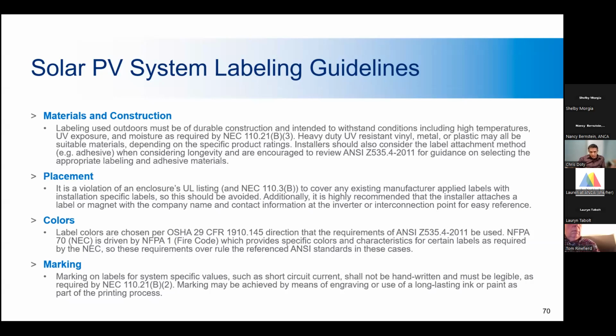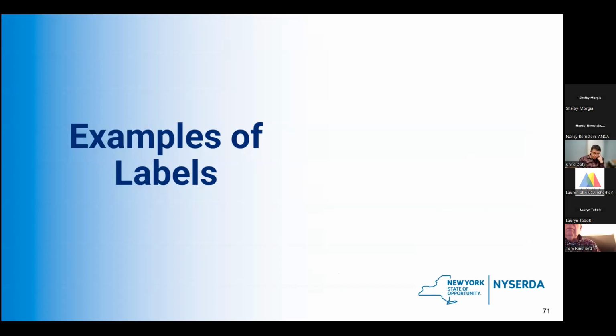And another thing to keep in mind is the most dangerous label is a wrong label. Missing a label is bad, but it's even worse to have a wrong label, because that'll give the person working on the system a sense of security that they know what's there. And if it's wrong, it can cause shock hazards and potentially injuries or death. So you need to make sure that you have all your labeling correct, and make sure that none of them are incorrect. So now we'll go through a bunch of examples of labels. One thing to keep in mind is all of the solar PV signage is yellow, orange, or red in color, and that's so it's easily identifiable for electricians and code officials to find.